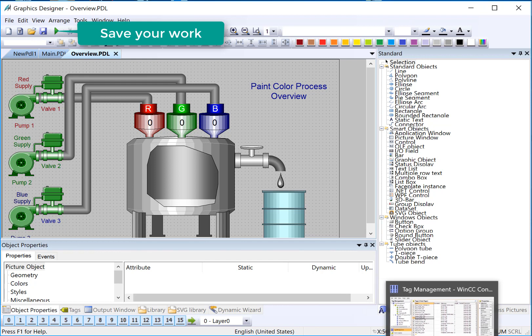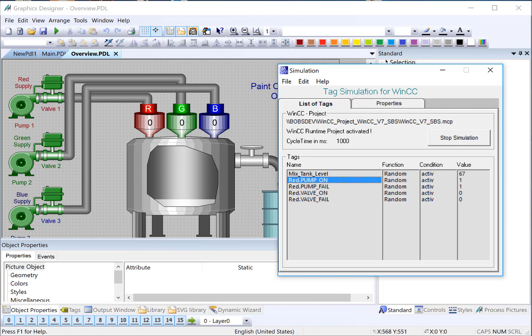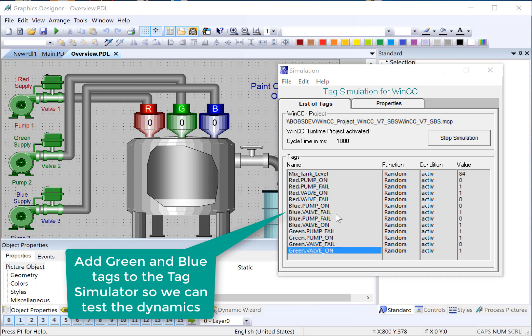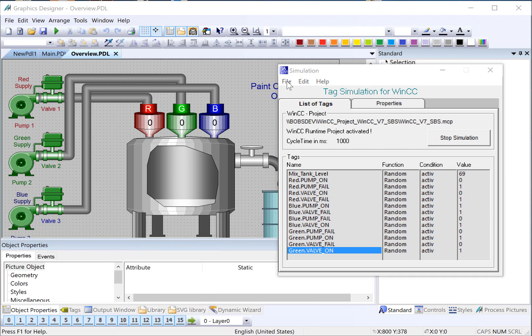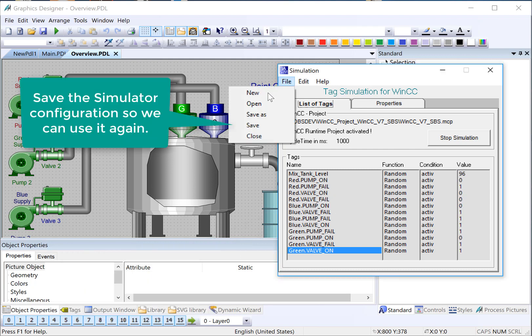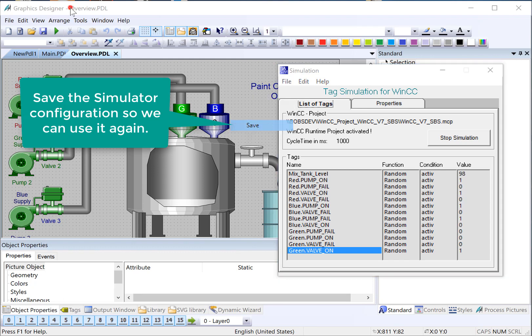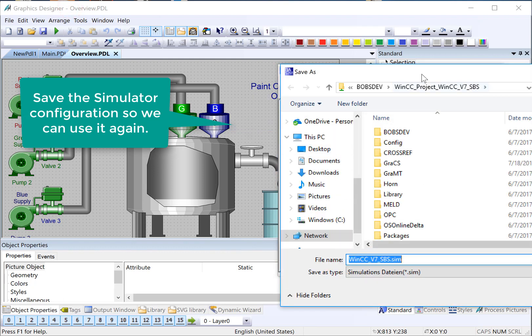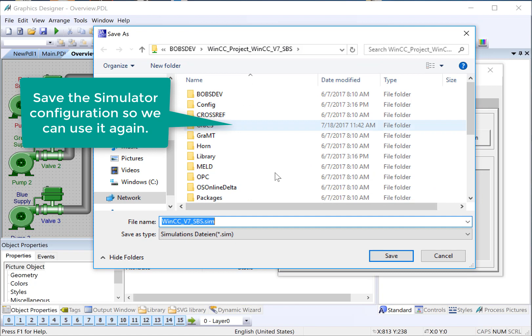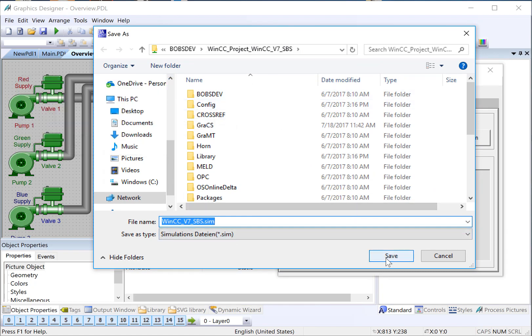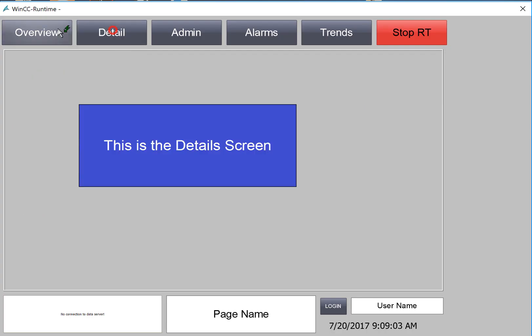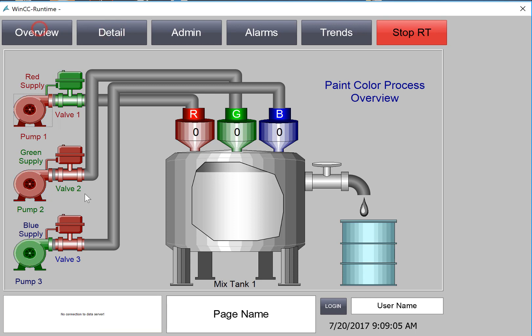And we have to update our simulator so that we are also simulating our green and blue tags. So let's do that. So I've used the same procedure to add my blue and green bits for my pump and my valve. And we really need to save this so we don't lose it. So I'm just going to choose Save. It will automatically just save in my WinCC project as a .sim file in my project folder. So I just have to hit Save once more and then we're good. We can recall this at any time. Going back to runtime, we can see that all our animation is working and so our dynamics are working.